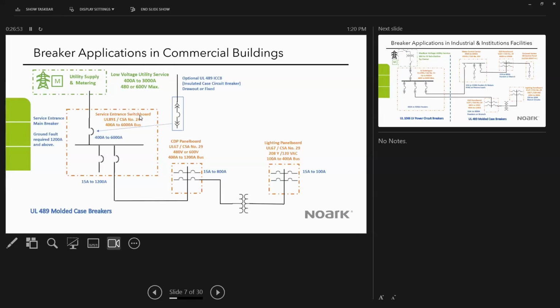In larger commercial buildings, what you see here is you have a much larger ampacity service. So the service entrance main can be up to 6,000 amps. And this is where that insulated case circuit breaker can come into play. So in a service entrance switchboard under UL 891, typically it's a molded case breaker as that main device. But if circumstances require a draw out or a larger ampacity breaker, often it's that insulated case breaker that's used as the main device. A switchboard is a single assembly that contains a cross bus and all of the distribution breakers. So this kind of replaces that single main breaker with a splitter trough and individual feeder breakers from it.